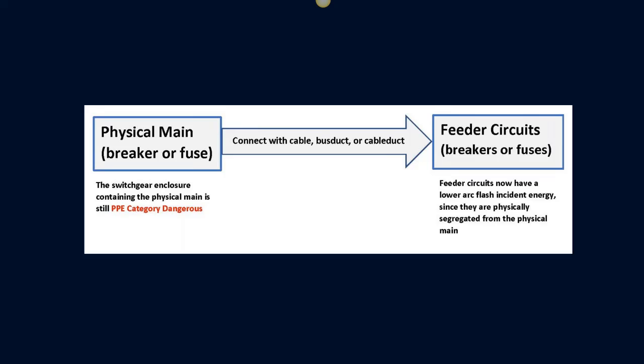I do believe that secondary virtual mains, although they've been allowed by the National Electric Code since the late 1940s, so this is not a new solution, but it is a solution that has gained rapidly in popularity since the publication of NFPA 70E in 2004, and of course the 2009, 12, 15, 18, and 2021 editions. The reason for this is, one, it's obviously safe space by eliminating a secondary physical main and replacing it with a secondary virtual main has space saving as well as safety benefits.